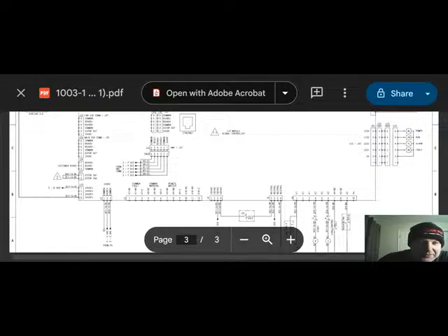So if you're coming in on common, coming out on normally closed, basically what that means is when this machine is off, you're going to have power flowing out this wire here, or when this machine faults, you will have power flowing out this wire here, and then when it opens, do the opposite. So if this machine is sitting here off, this is a dead contact, machine powers up, this powers up, and then when the fault comes along, just go away.